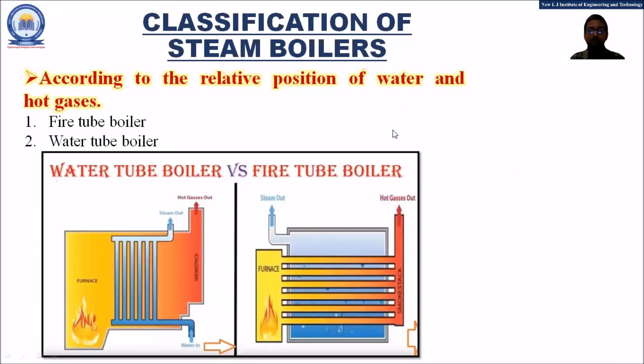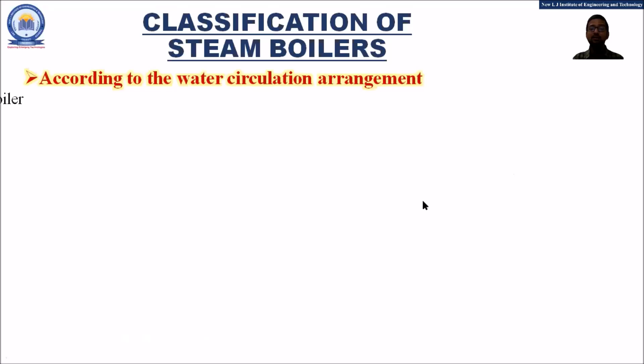Let us proceed further with the next classification, that is according to the water circulation. How the water is circulated inside the boiler. On the basis of that arrangement, the steam boilers are classified as the natural circulation boiler and the forced circulation boiler. In the natural circulation boiler, the water is circulated by means of gravitational force or by means of density differences. Naturally, the water will be circulated, so that is the natural circulation boiler. And in the boiler, if we are using a feed pump or other mechanical device to circulate the water, then that is considered as the forced circulation boiler.